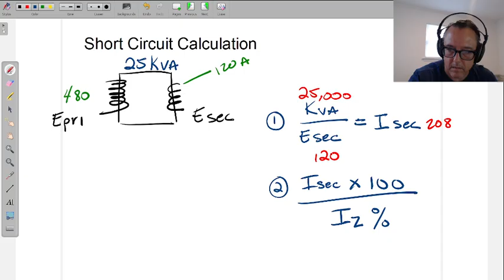Step two of the formula is I secondary times the constant multiplier of 100, divided by another fancy word, impedance percentage, represented as IZ. It means impedance percentage.